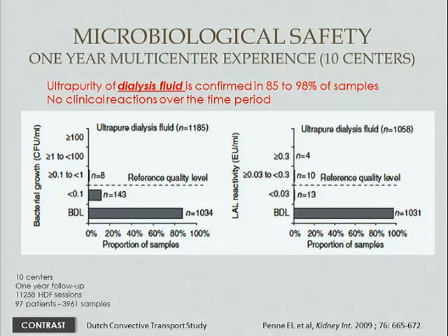Now it's possible to have what is really ultra-pure water without any detectable endotoxin. In other words, less than 0.03 endotoxin units.